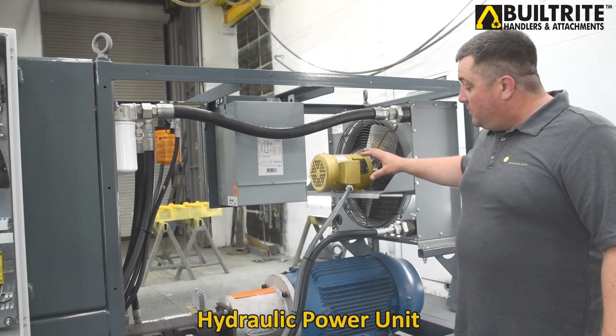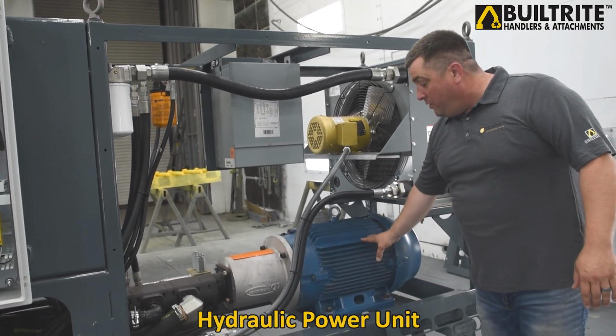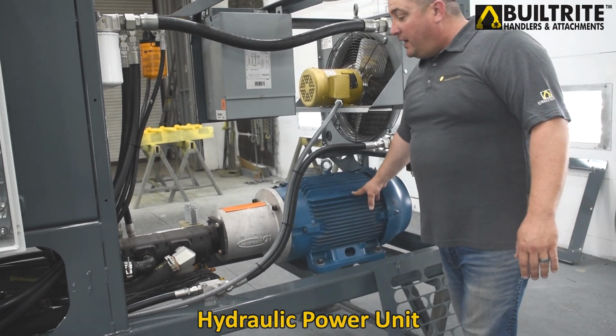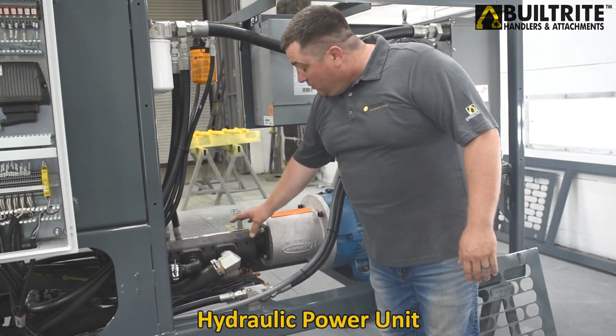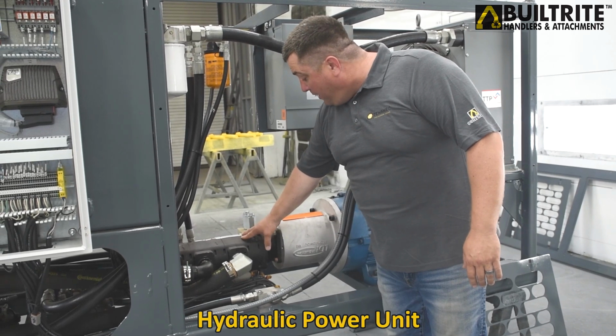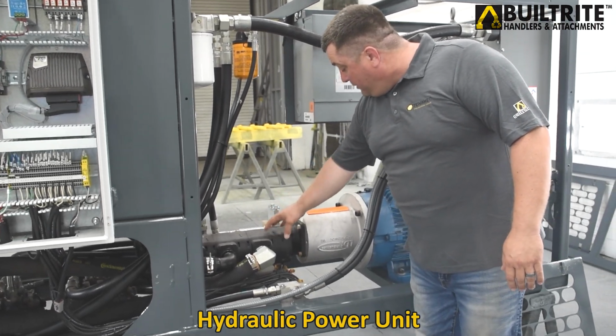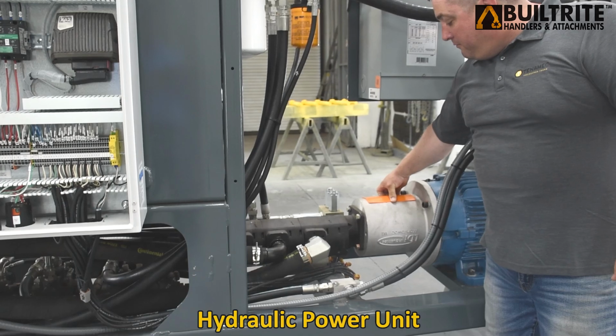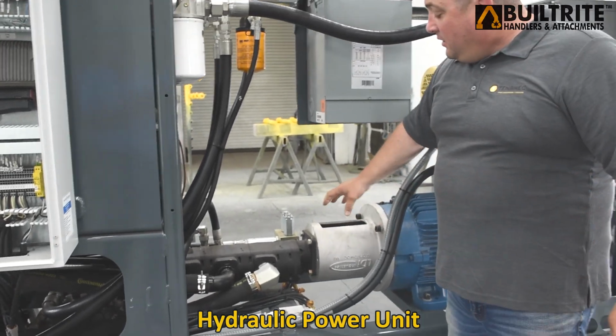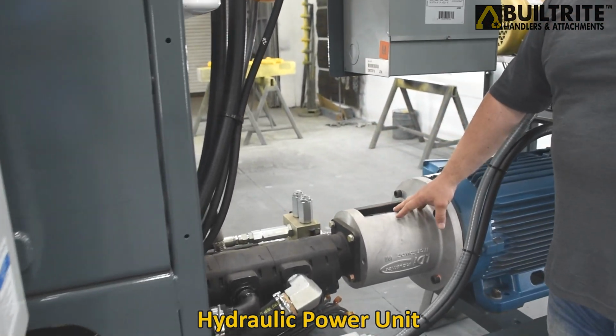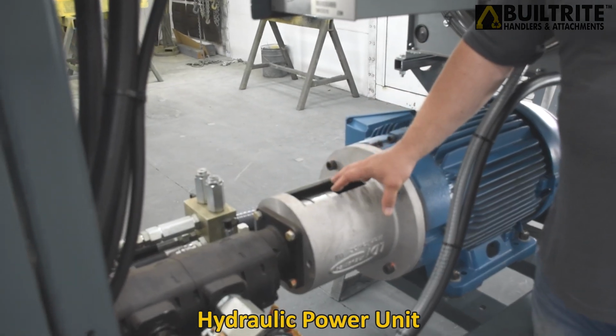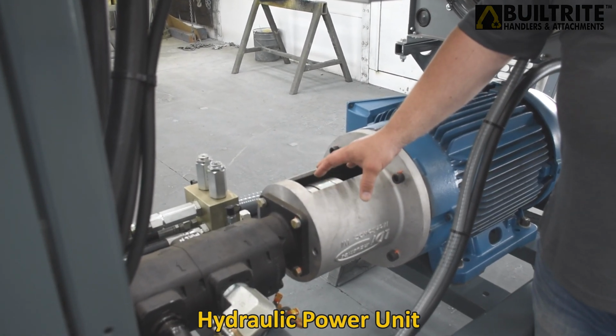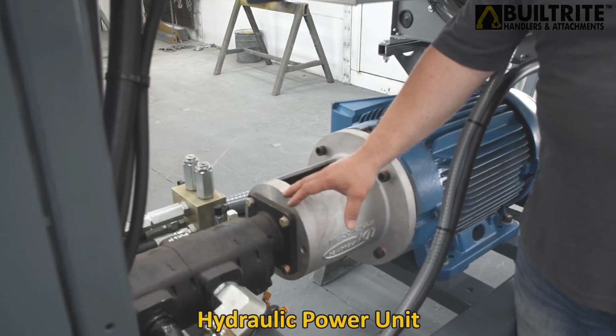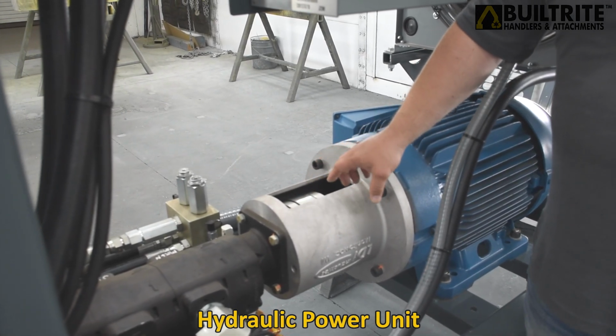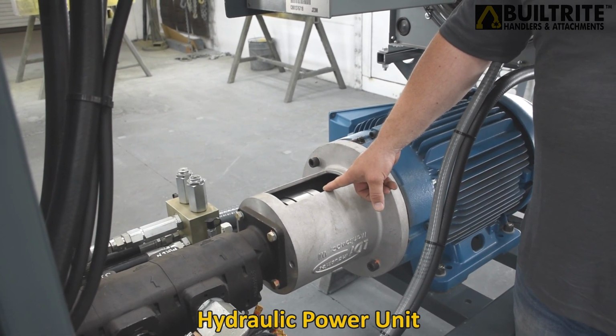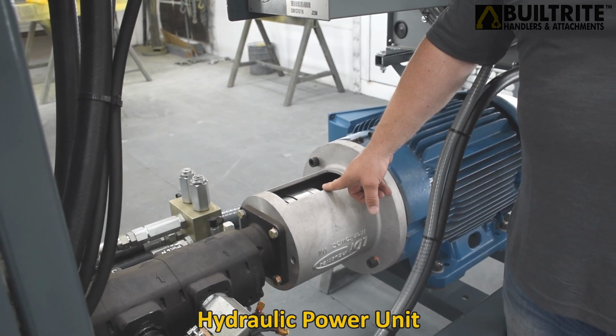Right underneath the cooler, we have our main motor, which is powering a triple gear pump, and in between the gear pump and the motor, we have a bell housing with an inspection port in it that you can view the coupling between the motor and the pump. We recommend that you do a visual inspection of this port every 6 months.